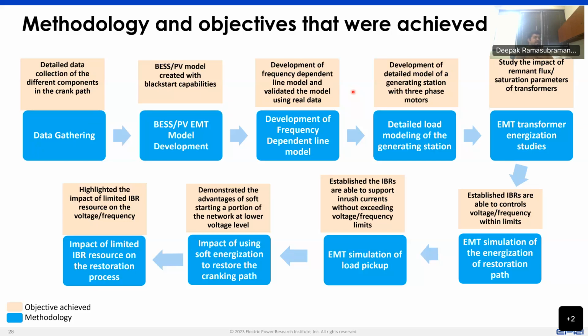Once we do that, look at the energization of the entire restoration path, look at if there is going to be a load pickup that is capable, evaluate if there needs to be a change in the restoration methodology. One of the crucial aspects of these kind of studies that we do is to try to understand that here is an existing restoration plan. What changes are required in that restoration plan when you have an inverter-based resource being the black start resource?